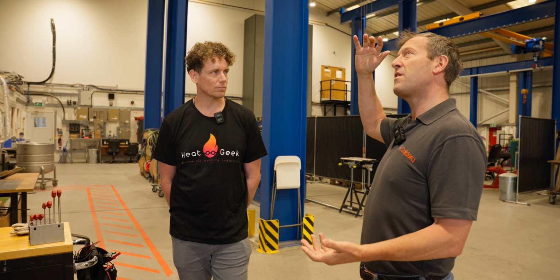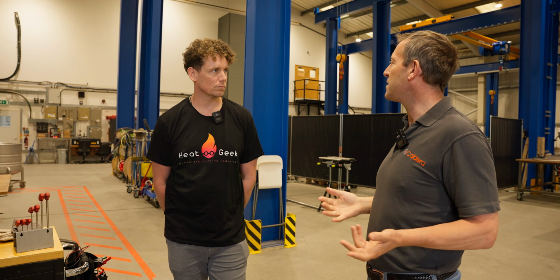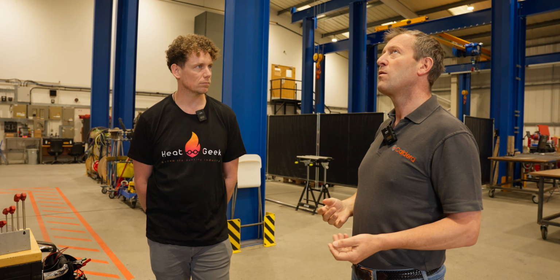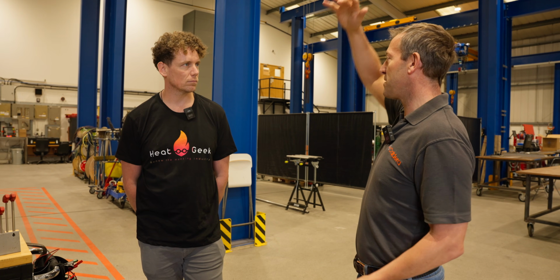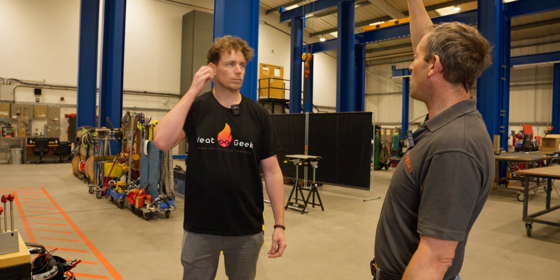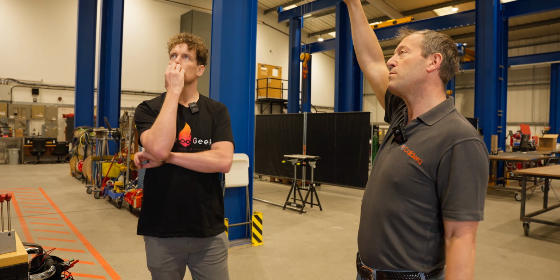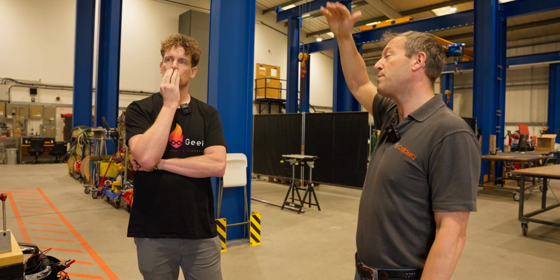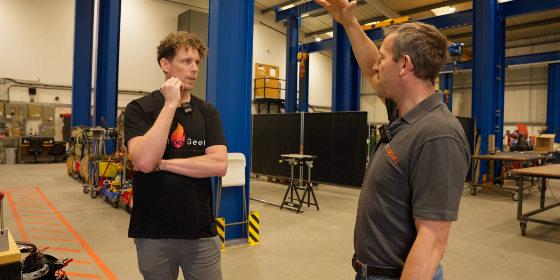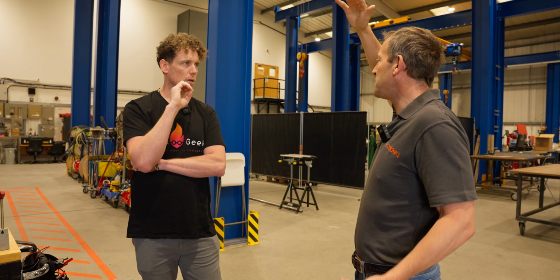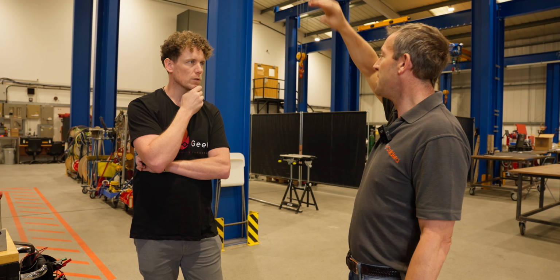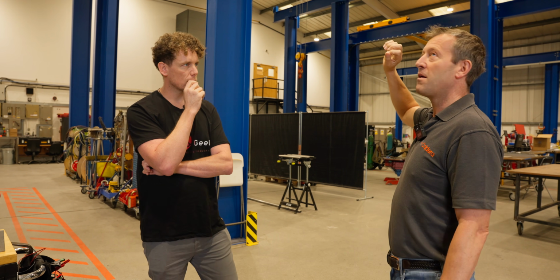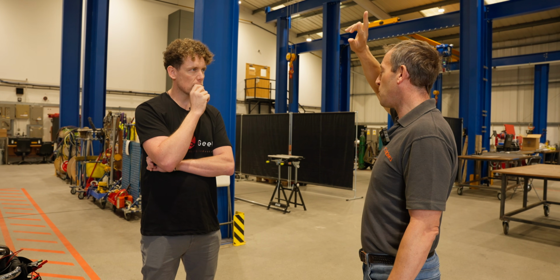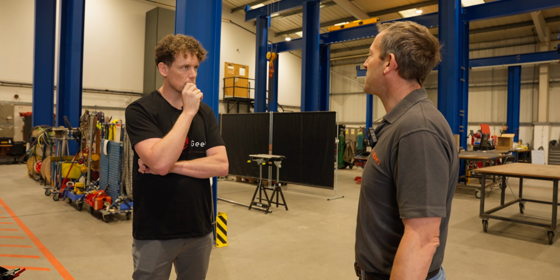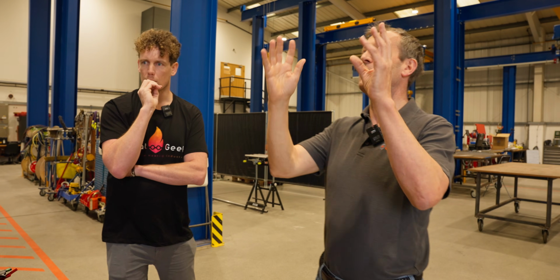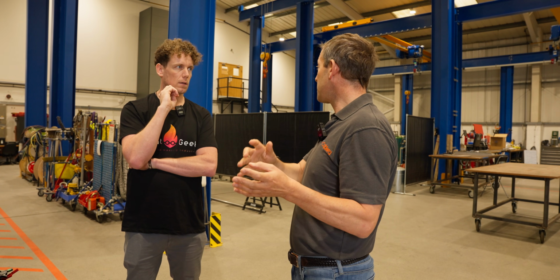With domestic, since most homes want heat at 50 to 60 degrees, we can get a bigger temperature range out of the storage material. The storage material never goes above 500. When making steam, we only go down to about 250, so there's a shorter range. When we're doing just hot water at 50 degrees, we can drop down to about 150, so we get a bigger range. This unit is 3 times as big by weight, but only twice as much energy when generating steam - so this is 200 kilowatt hours, and we've got 10 of them outside.